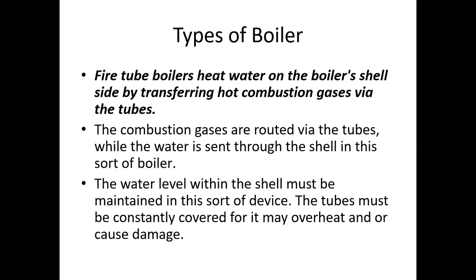Fire tube boilers, on the other hand, heat water on the boiler's shell side by transferring hot combustion gases through the tubes. What is inside the tube is your heat source — exhaust gas and hot combustion gases. The combustion gases are routed via the tubes while the water is sent through the shell. The tubes must be constantly covered or they may overheat and cause damage.